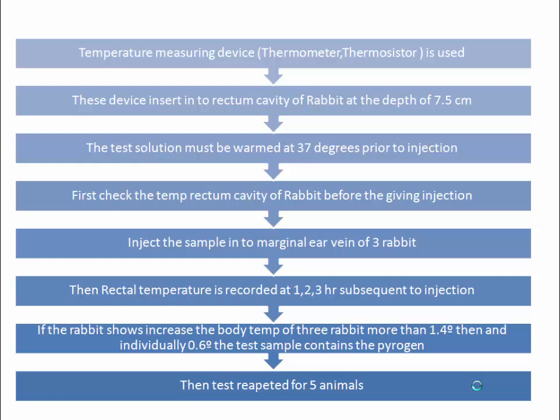After checking temperature at differential time intervals of one, two, and three hours, the final conclusion is made. If the combined temperature rise of three rabbits is more than 1.4°C, it confirms that pyrogen is present in the test solution. Individually, if any rabbit shows a body temperature increase of 0.6°C, that also confirms the presence of pyrogen. If pyrogen is found in the test sample, the test can be repeated on five animals.